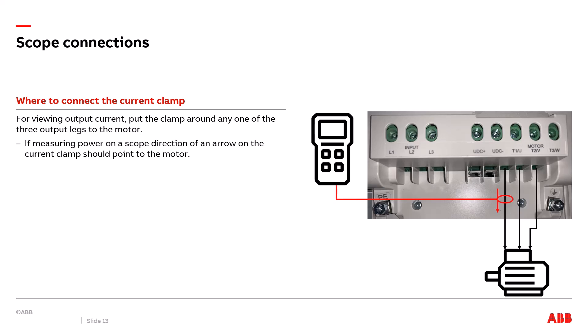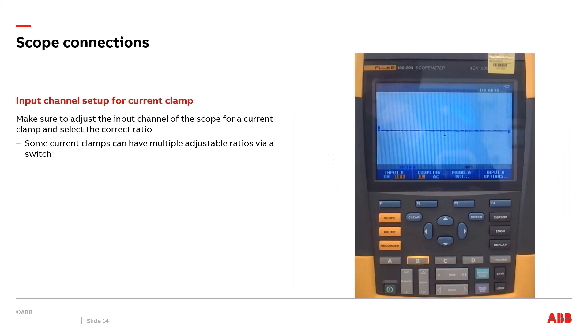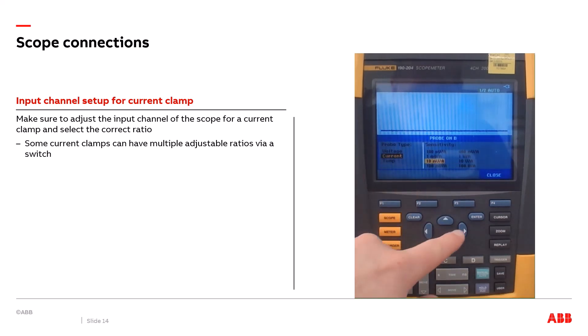Before looking at the current waveform, connect a current clamp around one of the motor wires — do not include the ground wire, only one wire. If measuring output power with your scope meter, make sure the arrow on the current clamp faces the direction toward the motor. Now set up the scope input channel to read the current waveform correctly. The current clamp can be set to read a max of either 40 amps or 200 amps via an adjustable dip switch, providing two different millivolts-per-amp ratios. Set the scope's input channel millivolts-per-amp ratio to match the dip switch setting on the current clamp.